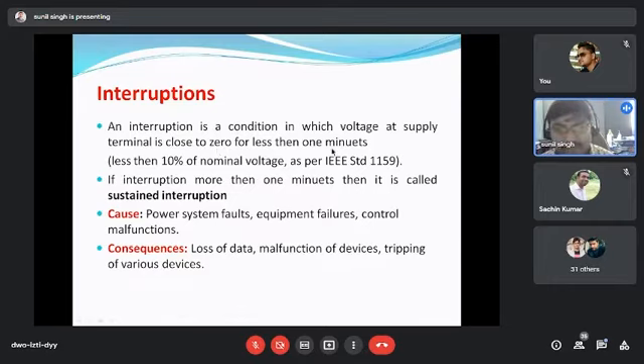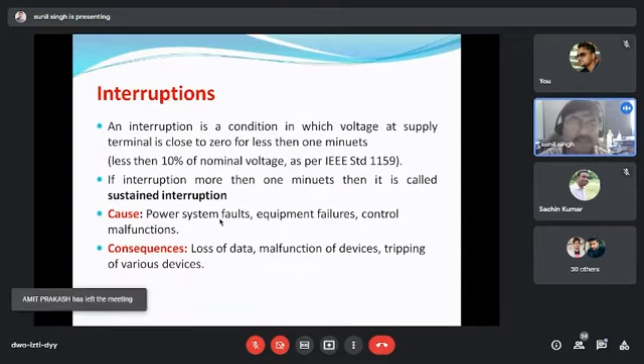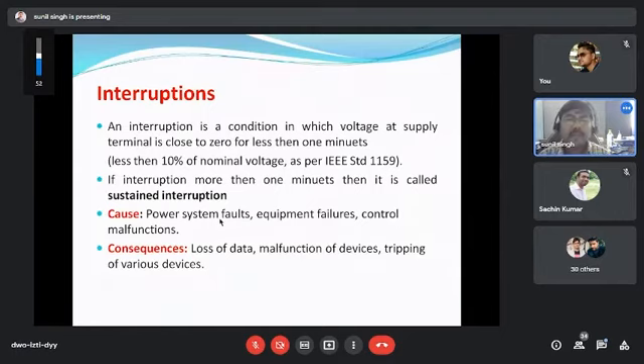If it is less than 1 minute, it is known as a short-term interruption. If it is longer than 1 minute, it is known as a sustained interruption. So what do sustained interruptions mean? That means some human intervention is required. Some fault is there, or maybe an intentional power cut, and human intervention is required to restore the supply.